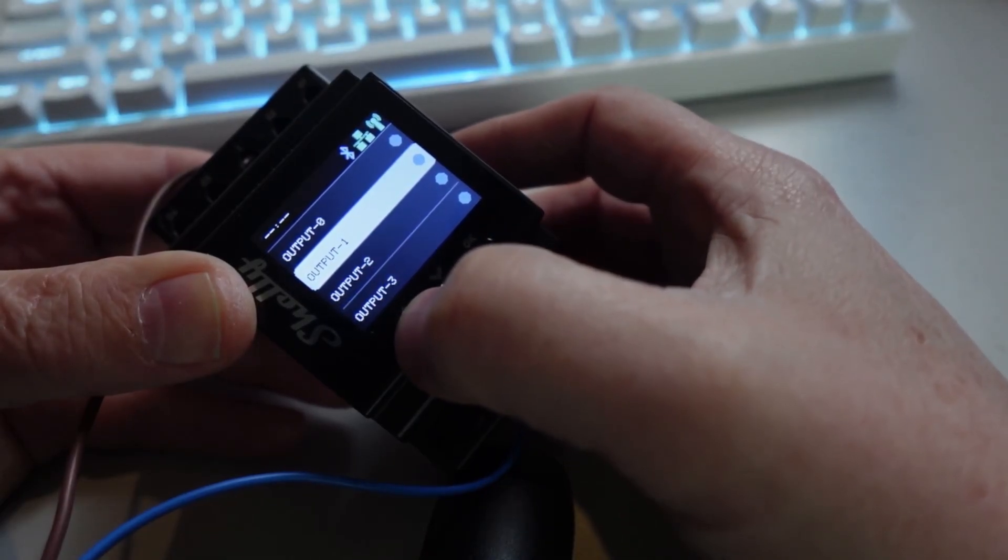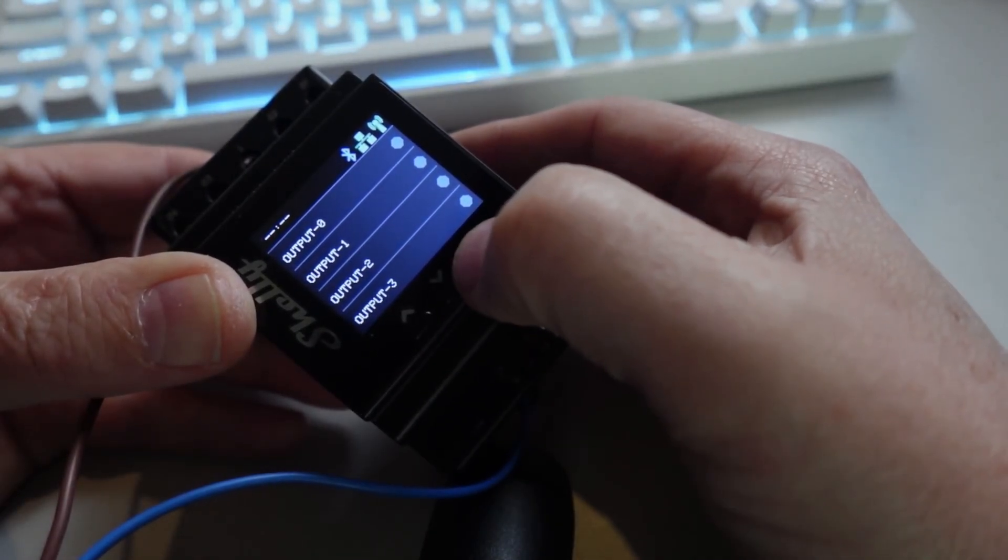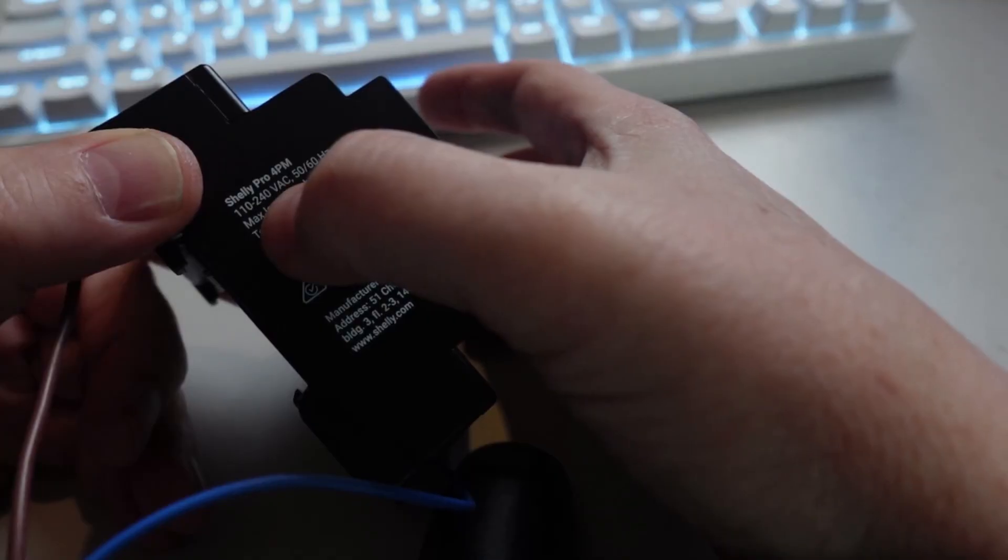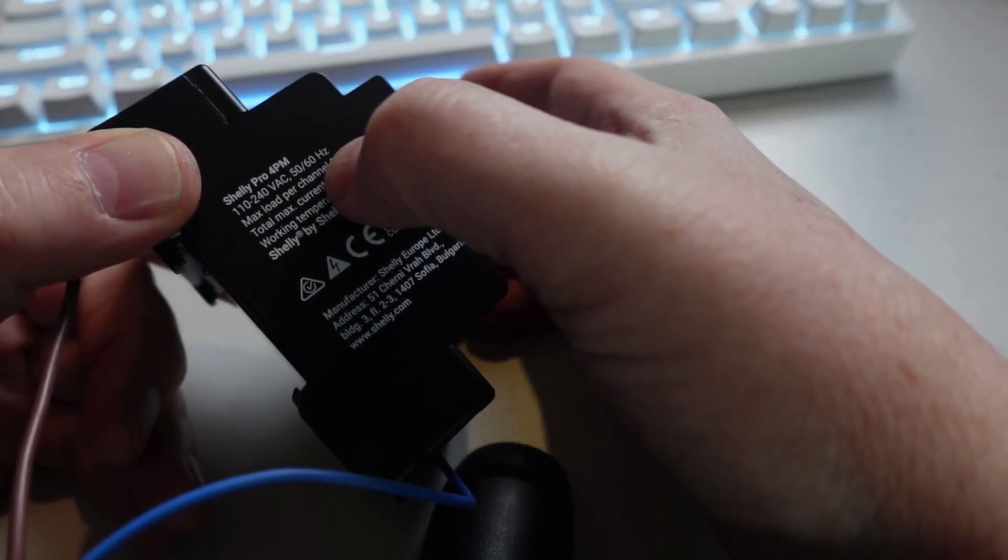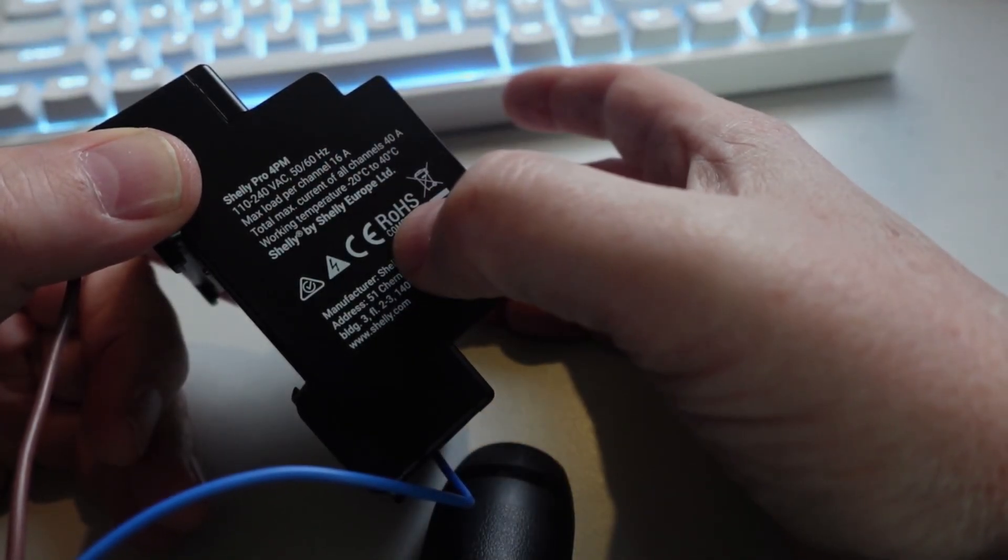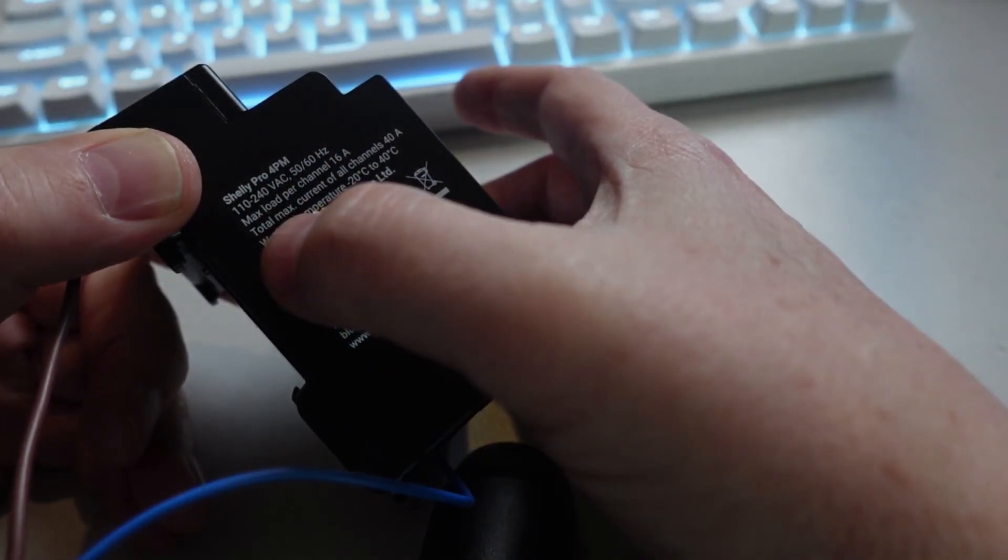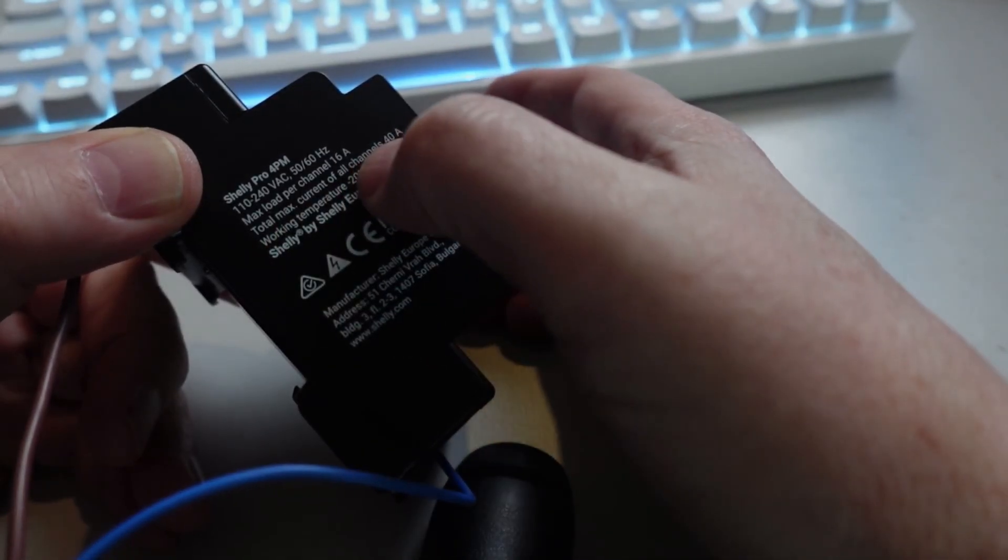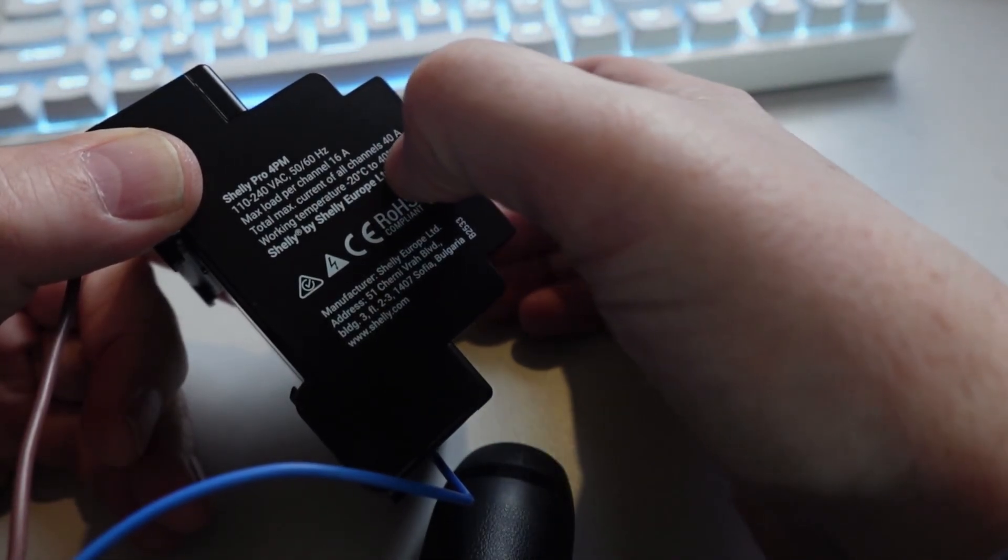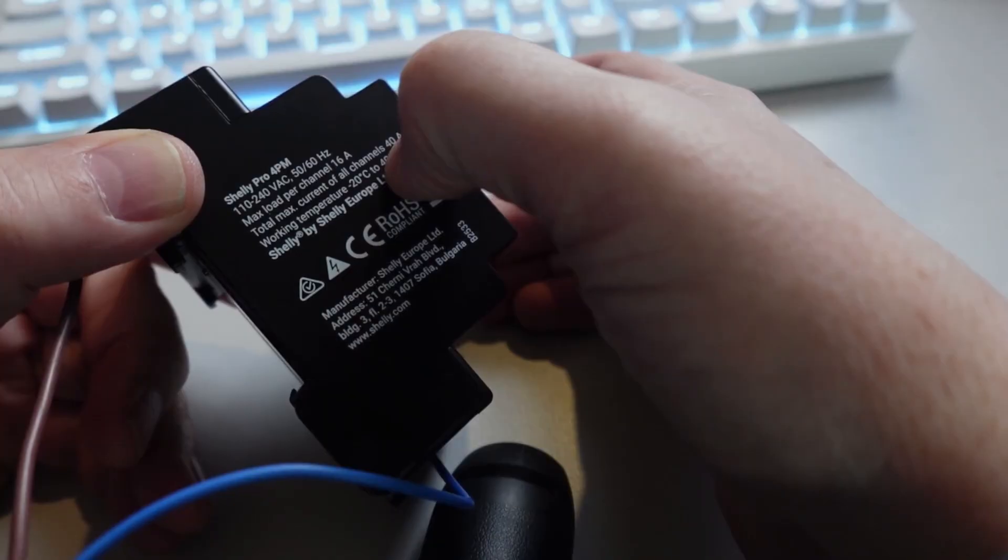Device is rated at 110 to 240 volts AC, 50 or 60 hertz, and do bear in mind that even though it's 16 amps per channel, the total device can only transfer 40 amps.